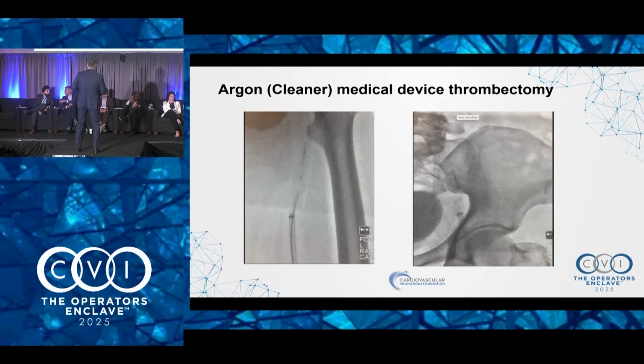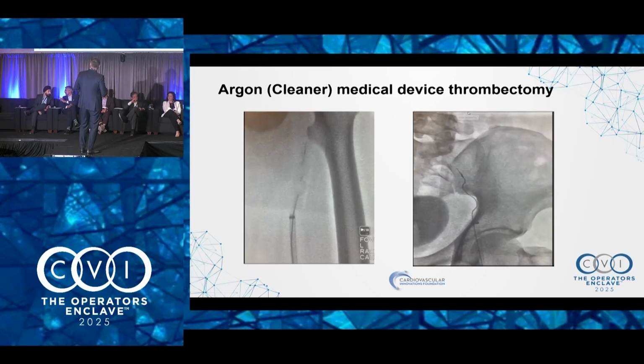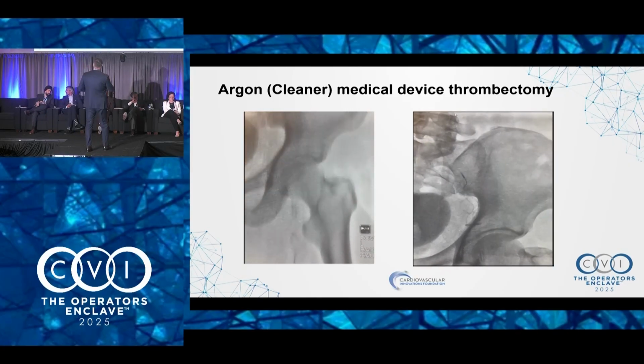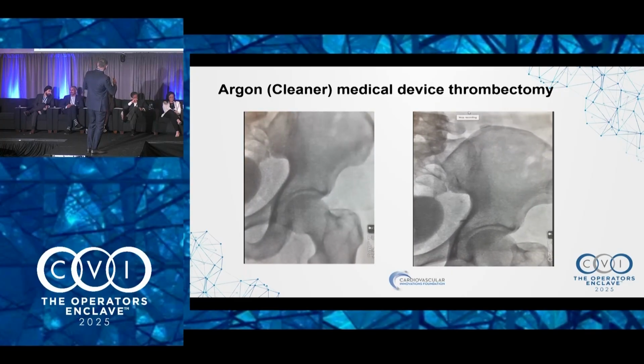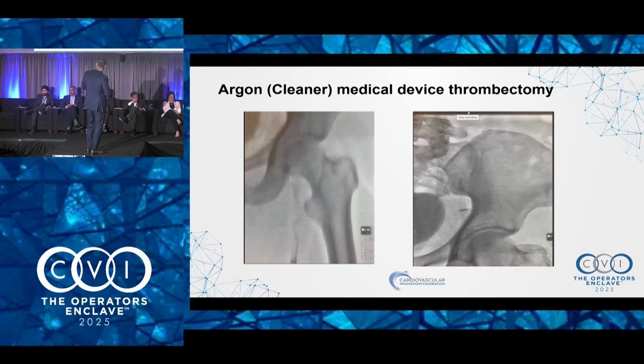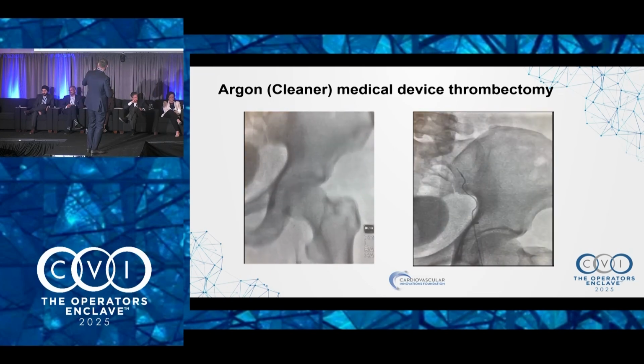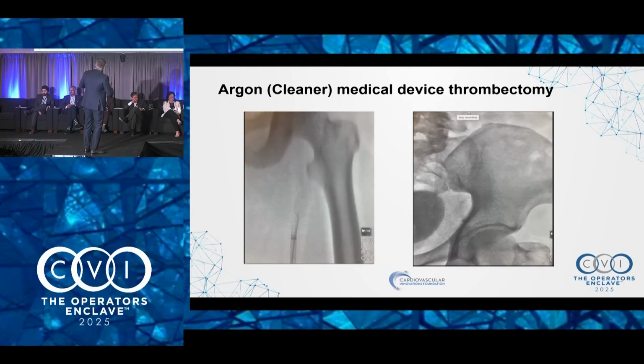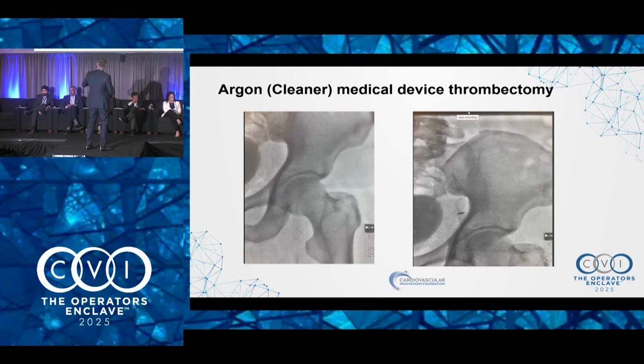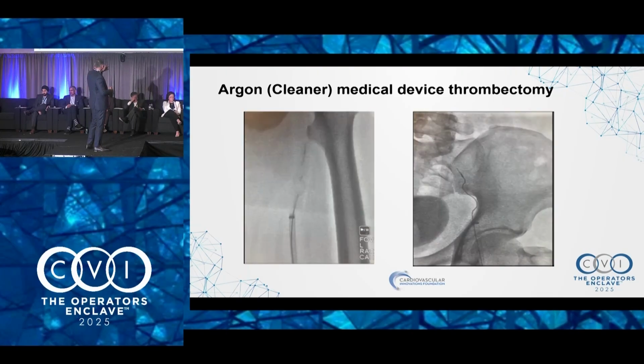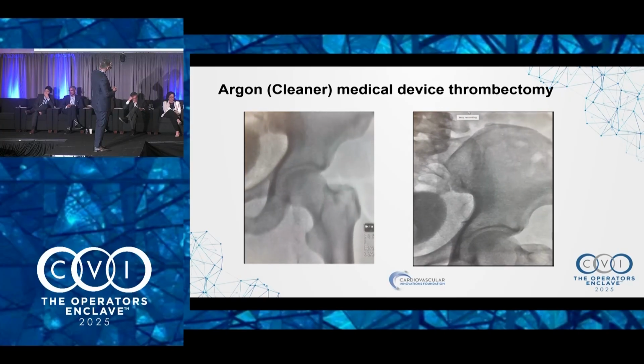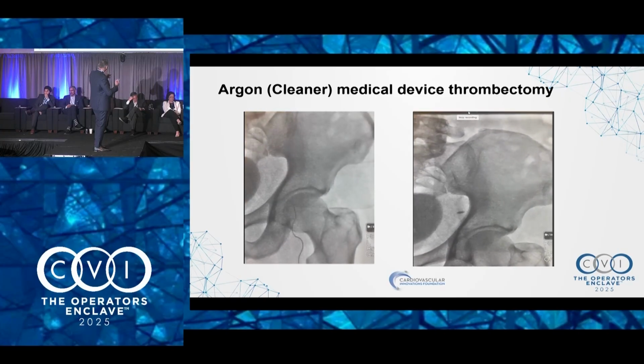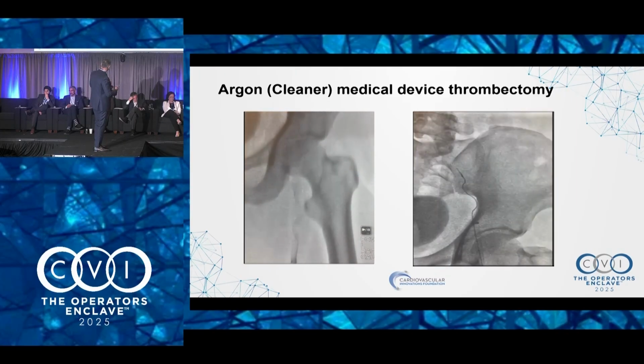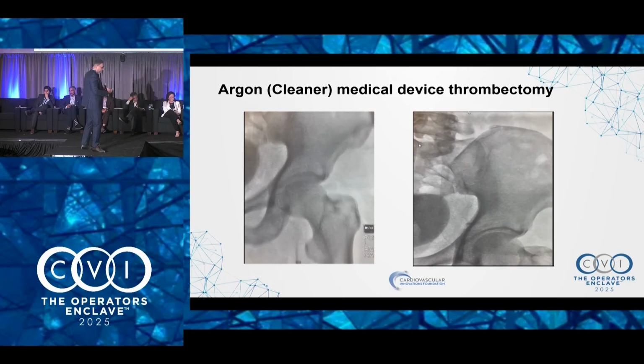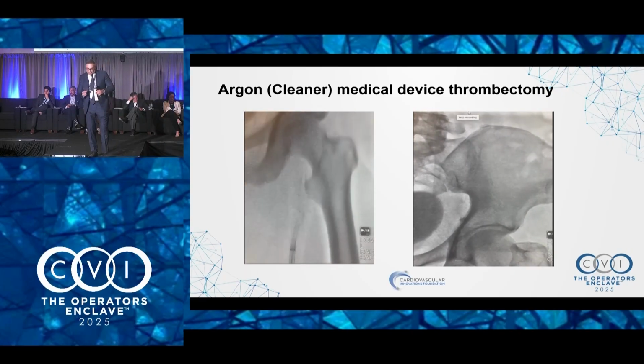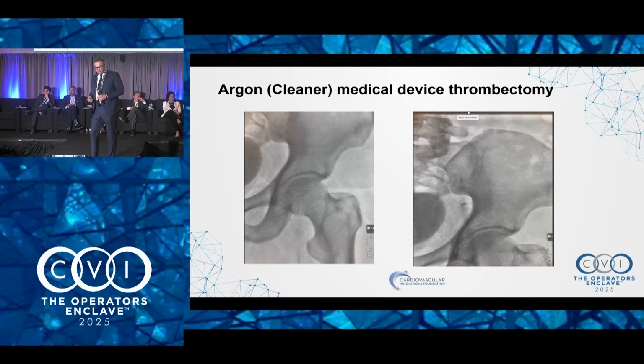So I was lucky to be able to use this newer device. I say lucky just because it's new, not because it's really anything different, but it's called the Argon Cleaner Medical Device Thrombectomy. It has a wire at the tip top of it, as you can see, that rotates in the vein, and you can just slowly advance it while going through the clot. Now, if you look on the left-hand side, you can see the wire rotating freely in that femoral vein all the way up, because there's no clot or barely some clot up at the femoral vein. When you look on the right-hand side, the tip of the wire, when it reaches the chronic clot, is more stable and not rotating as fast as the body of the wire underneath. So it's trying to do rotational atherectomy or rotational thrombectomy there, but I think it needs to be a little bit stiffer for later use.